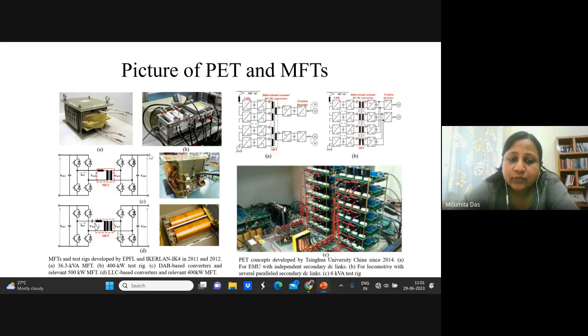This resonant converter allows the converter to operate at much higher frequency. In the resonant converter, there are different regions which allow the converter to operate in either inductive or capacitive region, and that gives a soft switching feature which allows the high power converter to operate at high frequency. That is why nowadays resonant converter based work is used for high power applications, because it allows the switches to operate in soft switching mode.